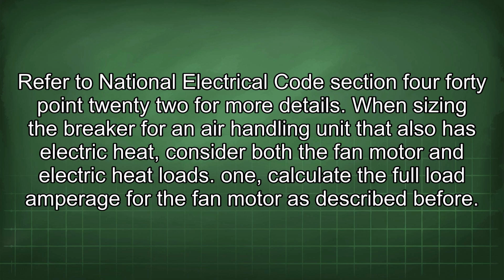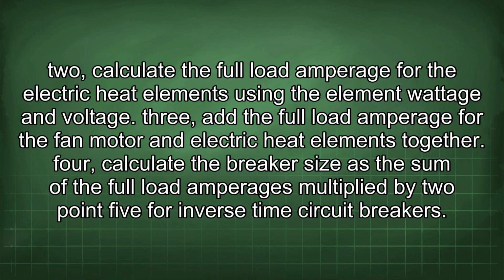When sizing the breaker for an air handling unit that also has electric heat, consider both the fan motor and electric heat loads. 1. Calculate the full load amperage for the fan motor as described before. 2. Calculate the full load amperage for the electric heat elements using the element wattage and voltage. 3. Add the full load amperage for the fan motor and electric heat elements together. 4. Calculate the breaker size as the sum of the full load amperages multiplied by 2.5 for inverse time circuit breakers.